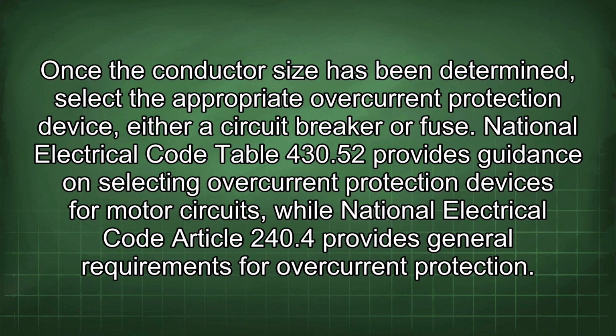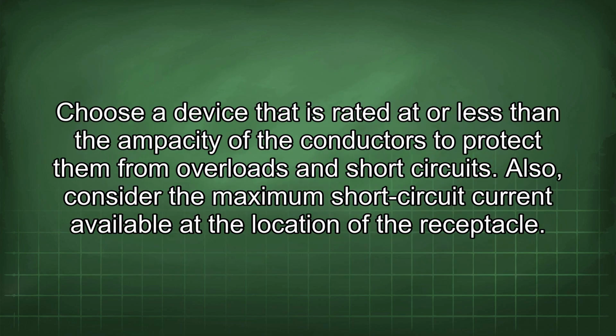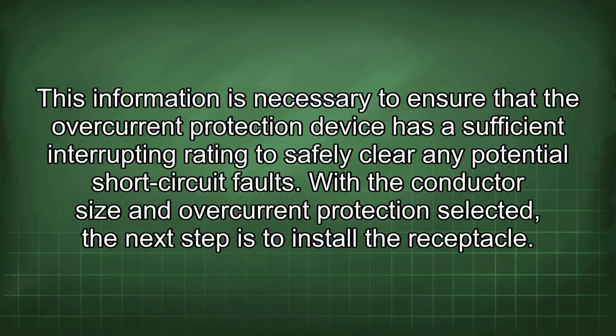Once the conductor size has been determined, select the appropriate overcurrent protection device, either a circuit breaker or fuse. National Electrical Code Table 430.52 provides guidance on selecting overcurrent protection devices for motor circuits, while National Electrical Code Article 240.4 provides general requirements for overcurrent protection. Choose a device that is rated at or less than the ampacity of the conductors to protect them from overloads and short circuits. Also, consider the maximum short circuit current available at the location of the receptacle. This information is necessary to ensure that the overcurrent protection device has a sufficient interrupting rating to safely clear any potential short circuit faults.